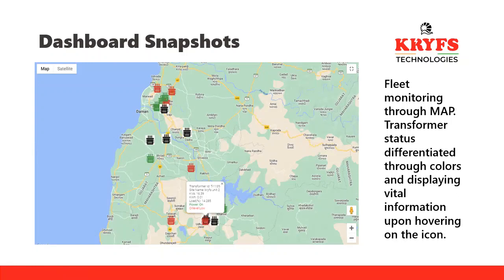There is also one very good feature of the map notification, which we can see, where all the transformer fleet is displayed on the map along with the location. It can be zoomed in to have a very close view. If you hover your mouse on a particular transformer, actually it will display the important parameters of that particular transformer and the alert which is being generated on that. Transformer are color coded, so black one represents the transformers which are offline, green represents the transformer which is healthy, and red represents the transformer which is having an alert. Okay.